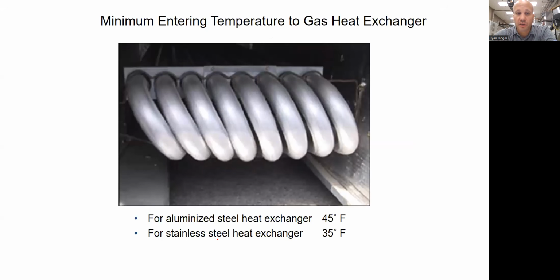Like I said, you need a stainless steel heat exchanger if you're going to be experiencing colder air. This is air entering into the heat exchanger. So you have return air and outside air mixing and then going into this heat exchanger. So maybe if you have a lot of outside air, say like 30% outside air, and it's Boston, so it's 5 degrees or something in the winter, that's a lot of outside air. I might have to do this stainless steel version.